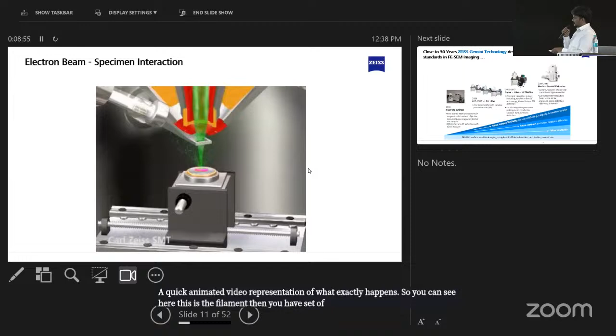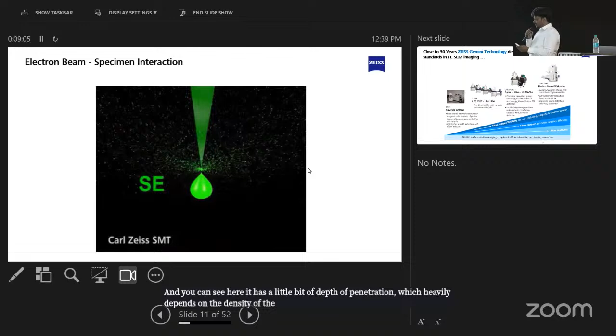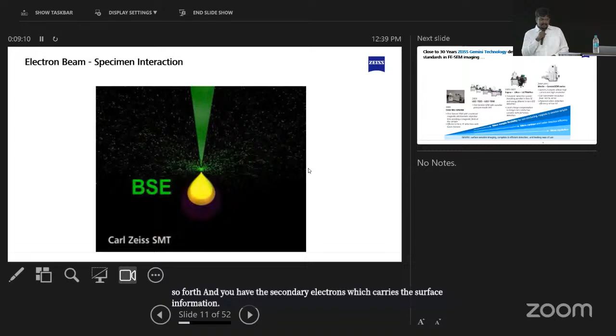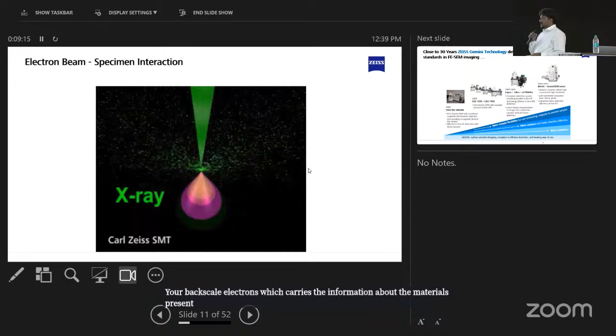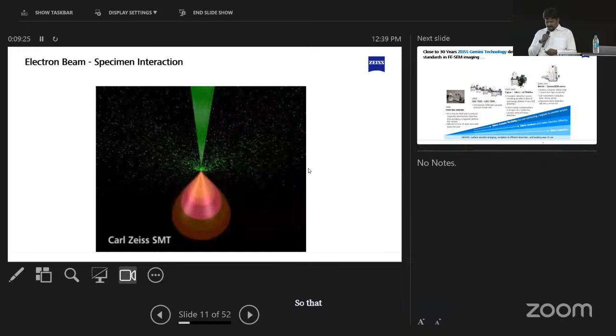You can see here, this is the filament. Then you have a set of columns through which the green color electron beam comes and interacts with your sample. It has a little bit of depth of penetration, which heavily depends on the density of the material, energy of the electron beam, and so on. You have the secondary electrons, which carry the surface information. You have backscatter electrons, which carry the information about the materials present in your sample. Then you can start collecting other analytical information like X-rays, cathode luminescence, Auger electrons, whatever you want to collect. So that's a quick representation of how the electron beam interacts with the sample.